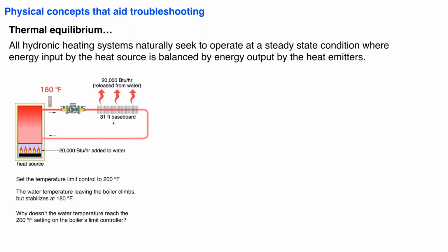Let's start off with a pretty simple example here. We've got a heat source, I'm showing it over here. It could be a boiler, it could be a heat pump. It doesn't really matter. It's something that is generating 20,000 BTUs per hour and adding that to a stream of water. And out here, we've got 31 feet of fin tube baseboard, let's say a residential baseboard.